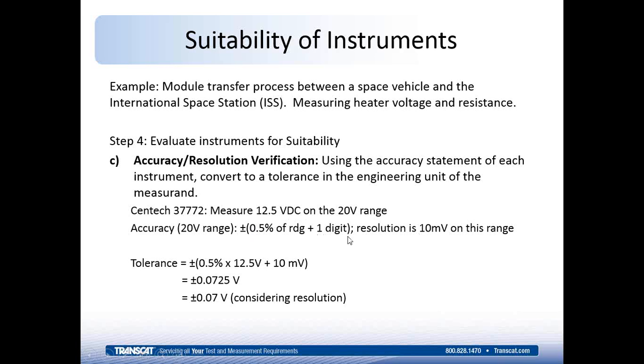So taking that accuracy statement and converting it to a tolerance using the 12.5 volt measurement that we'd be making, multiplying the 0.5% times 12.5 volts and adding 1 digit of resolution, which is 10 millivolts, comes out to 0.0725 volts. And now rounding that to the resolution of the instrument at 10 millivolts would give us plus or minus 0.07 volts. That's what the manufacturer states the instrument can perform to for that particular range and that particular voltage.